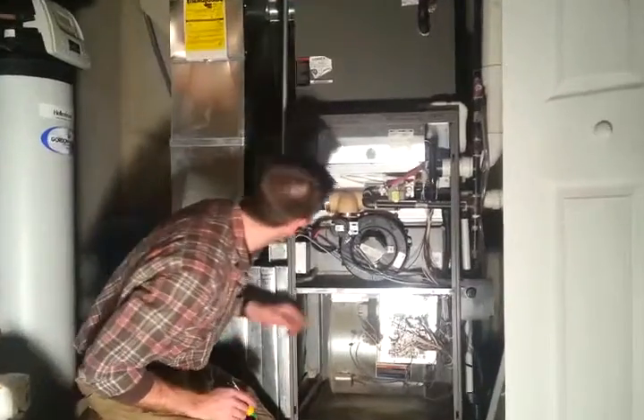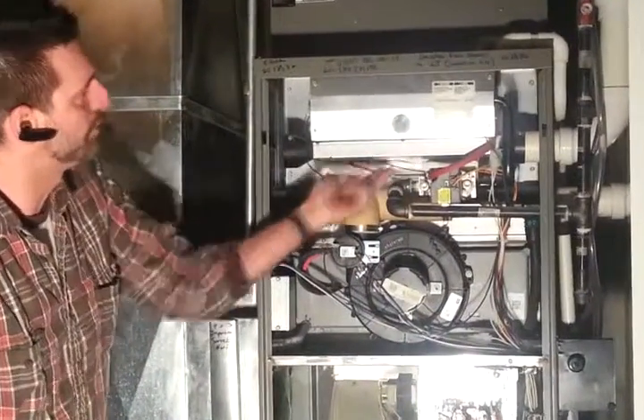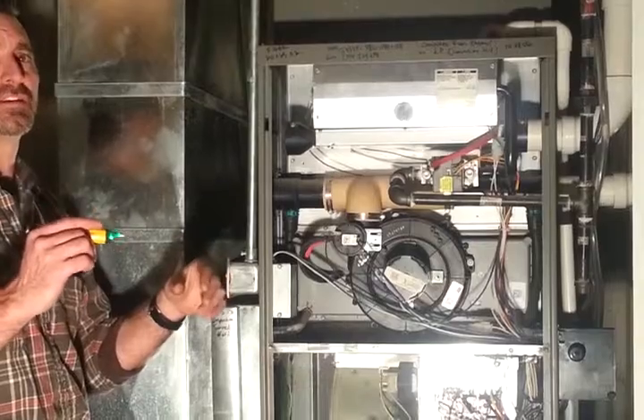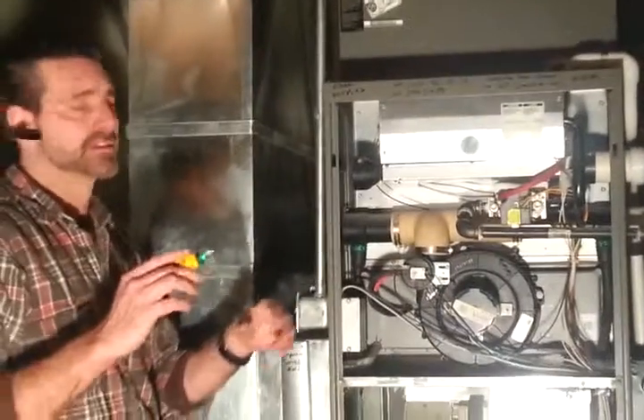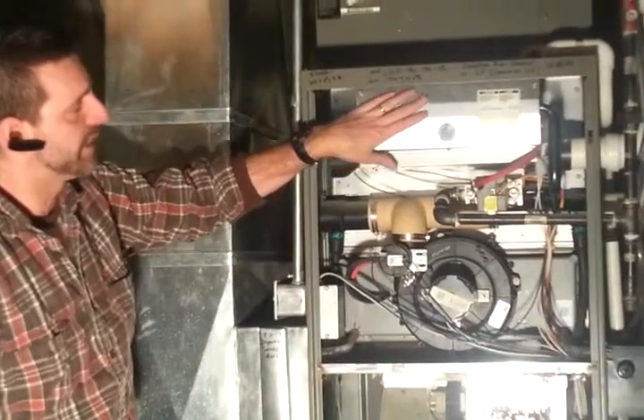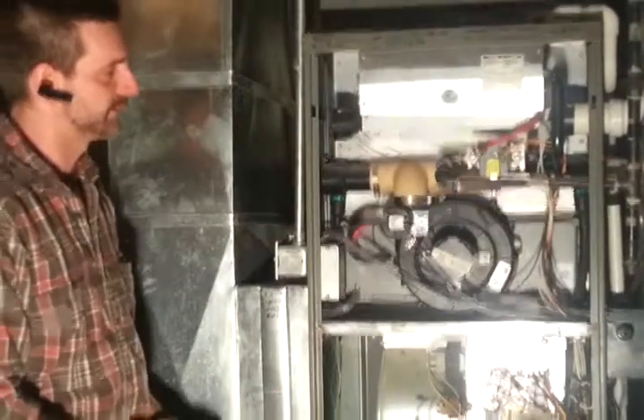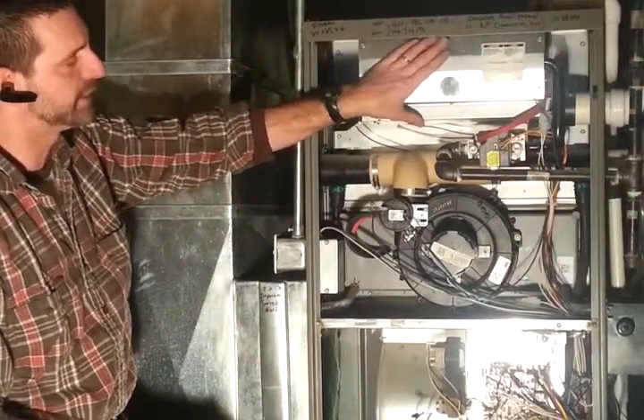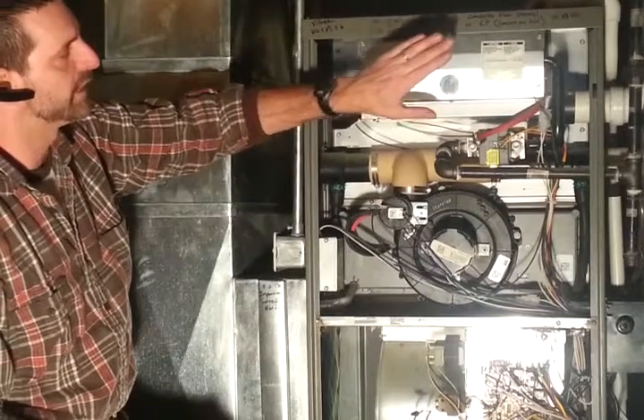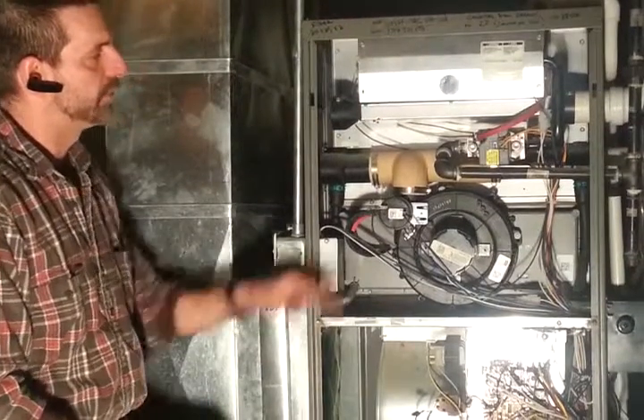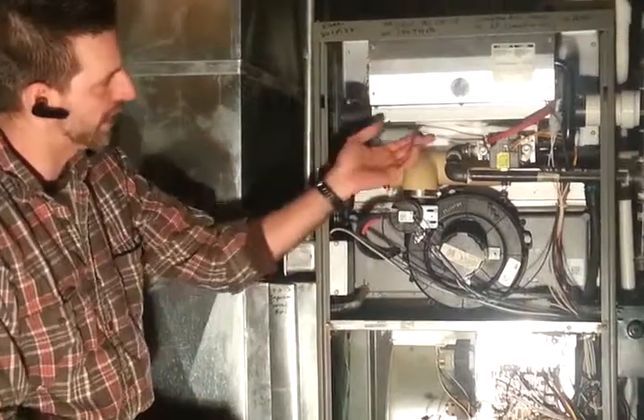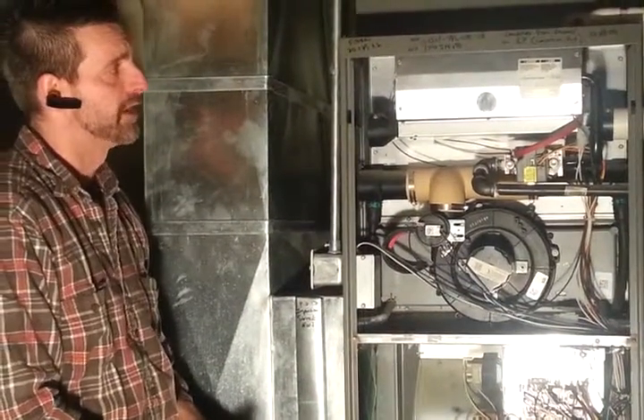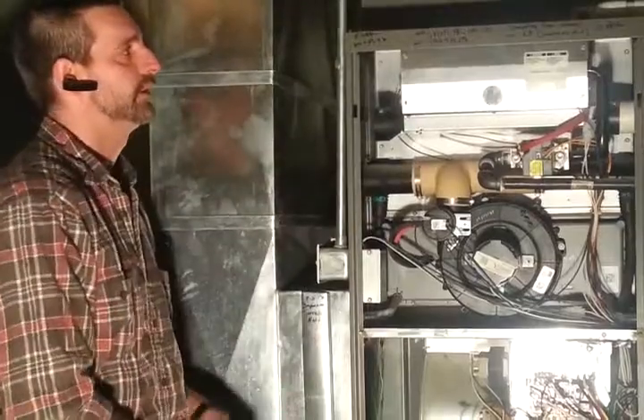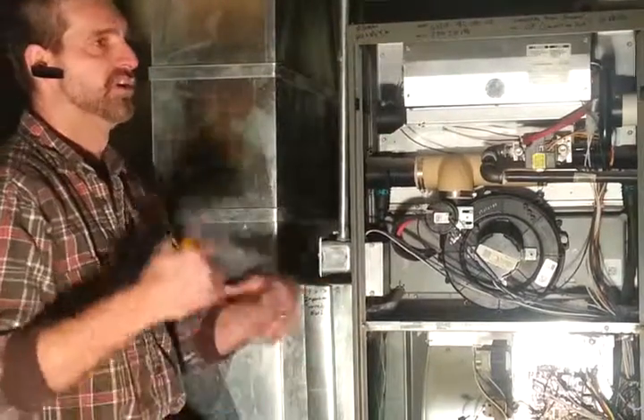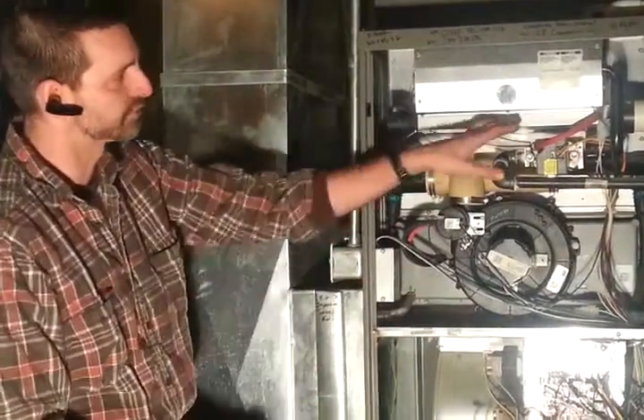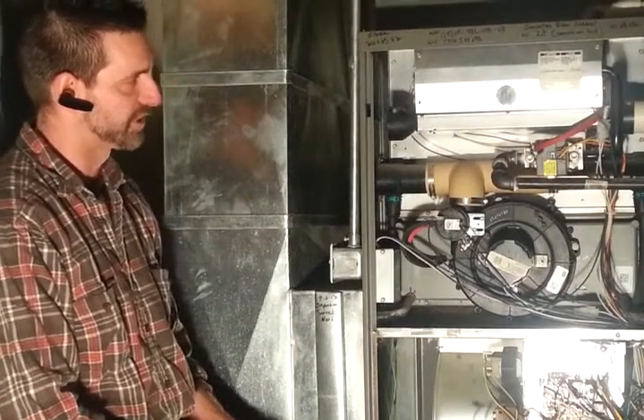Some other things to note. There is a flame detection sensor that's up in my combustion chamber. It takes that flame and makes sure that there is actually a flame. If there wasn't a flame, it would shut your gas valve down. So that flame detection sensor is very critical. If we were to see your burner ignite for a few seconds and then shut off, we would suspect our flame detection sensor.